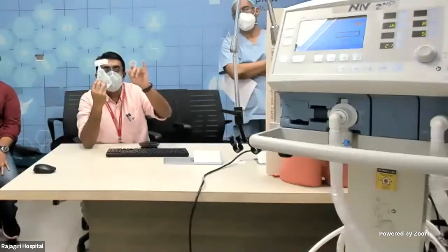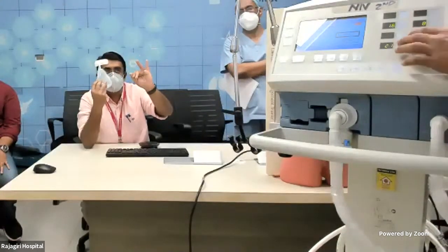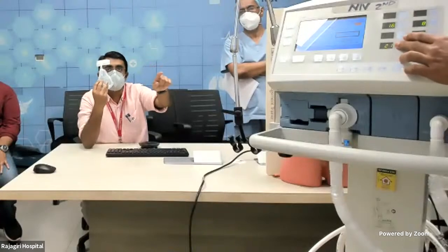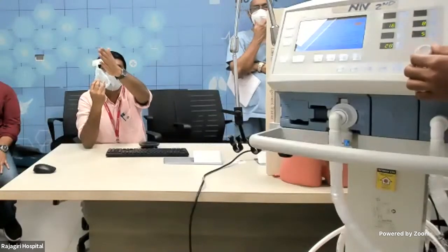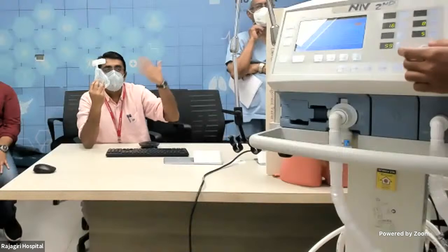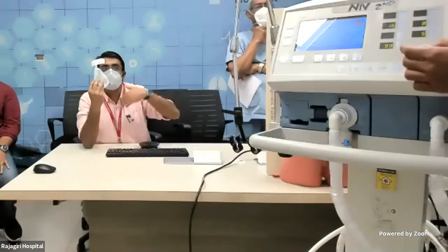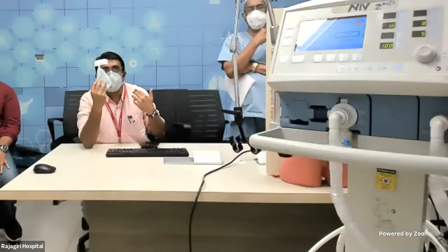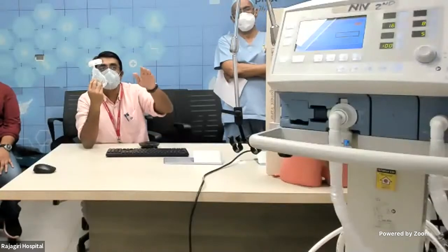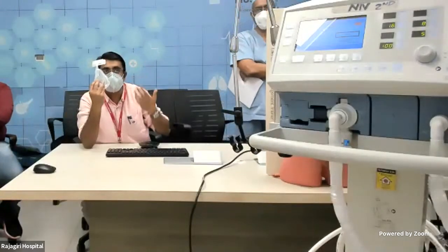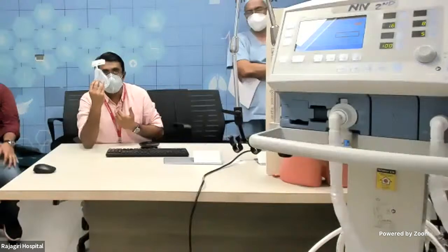Oxygenation, remember, oxygenation is one thing, ventilation is second thing. Oxygenation you can adjust in the machine because FiO2 can be adjusted from 21 to 70, 80, whatever you want, to get a saturation of 90 to 96, what we aim for in a pregnant patient. However, the ventilation part is important. By this pressure adjustment, you get the ventilation correct, which makes the patient comfortable.